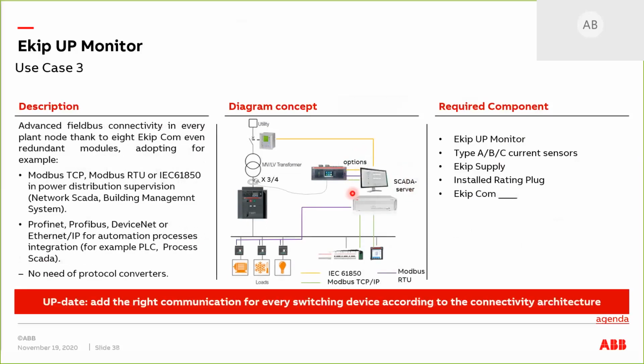Okay, the other thing that we can do is integrate it with the SCADA server. The SCADA server could be an IEC 61850 because we have those protocols, so we can do the communication. If the SCADA server is IEC 61850, or either a Modbus TCP/IP or a Modbus RTU, then our Ekip UP is actually capable of sending the information that we have for the circuit breaker to the BMS.